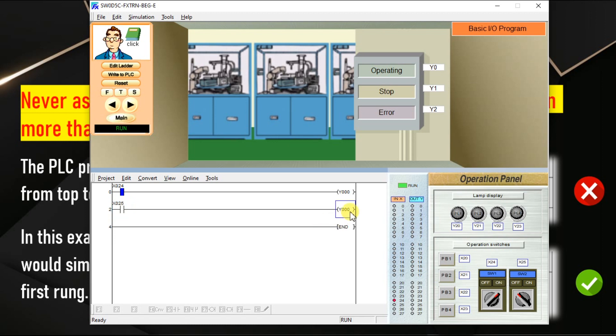And output is updated accordingly. So if you use the same logic in real time with this type of PLC, what happens? Your output Y0 will only respond to input X25. The output Y0 will not respond to input X24. That means part of your logic is not going to work. It leads to problems. The machine may not work properly as designed.